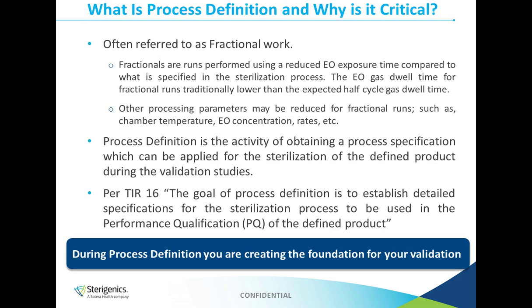Now, what is process definition and why is it so critical? Process definition is often referred to as fractional work, and fractional runs are performed with reduced EO exposure time compared to what is specified in your sterilization process. So the EO gas dwell time for your fractional runs is traditionally lower than what you see for your half-cycle gas dwell time. Now, when you perform fractional runs, a lot of times other process parameters such as EO concentration and chamber temperature can also be adjusted.